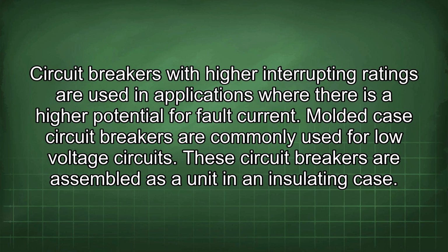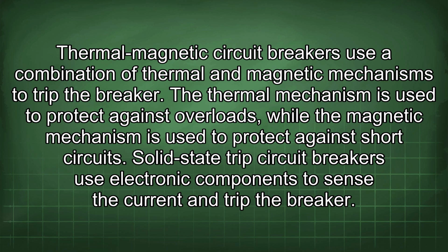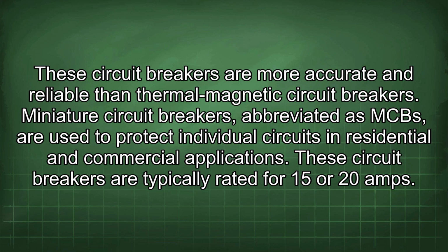Molded case circuit breakers are commonly used for low voltage circuits. These circuit breakers are assembled as a unit in an insulating case. Thermomagnetic circuit breakers use a combination of thermal and magnetic mechanisms to trip the breaker. The thermal mechanism is used to protect against overloads, while the magnetic mechanism is used to protect against short circuits. Solid-state trip circuit breakers use electronic components to sense the current and trip the breaker. These circuit breakers are more accurate and reliable than thermomagnetic circuit breakers.